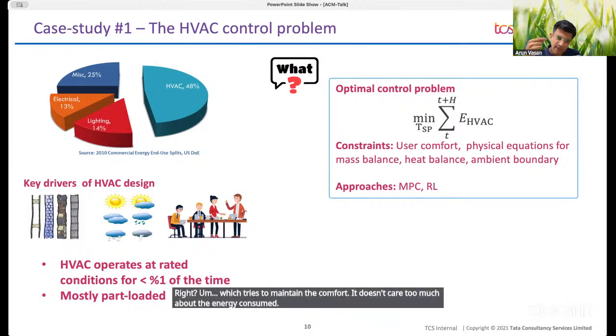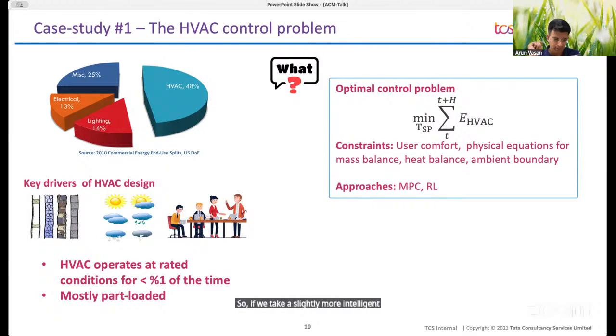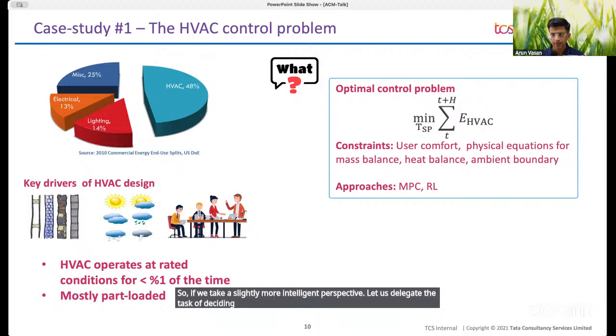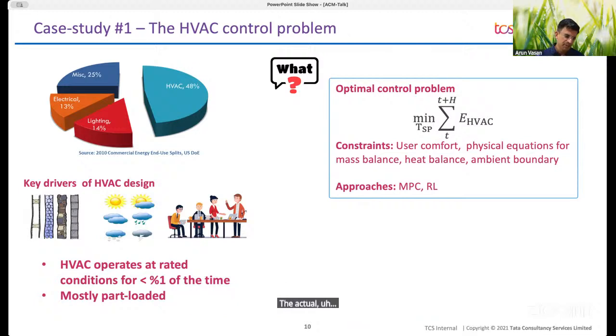So if we take a slightly more intelligent perspective, let us delegate the task of deciding the actual flow rate of the air handling units, the actual VFD speeds if required, etc., to the BMS controller. But I can operate at one level above the BMS controller and dynamically decide the set point. Now what do I mean by dynamically deciding the set point?